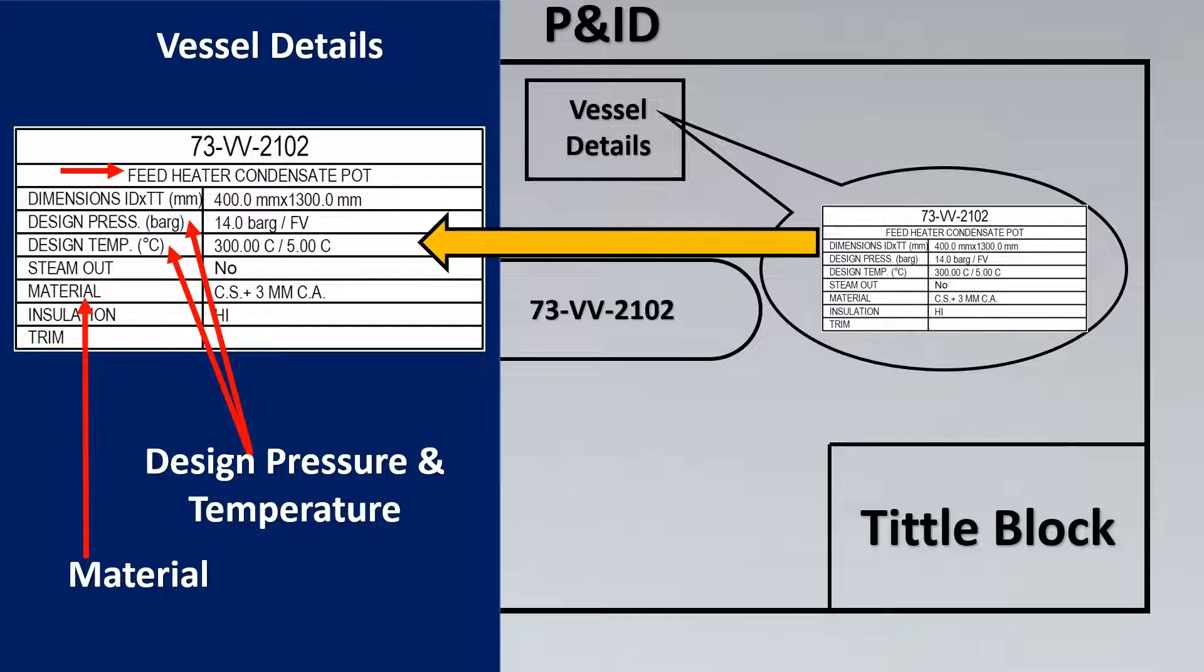Then the next thing is the material which is very important. If you see here it's mentioned CS plus 3mm CA. The CS stands for carbon steel plus 3mm CA stands for 3mm corrosion allowance. So even if indeed of corrosion is there, you have this much amount of thickness already available to mitigate the corrosion issue.